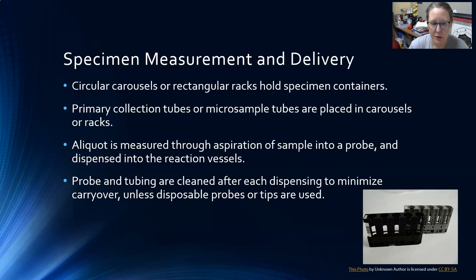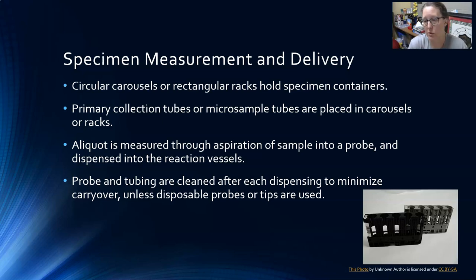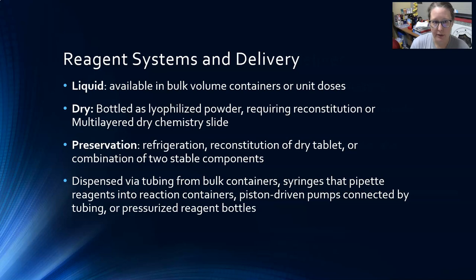The probe and tubing should be cleaned after each dispensing to minimize carryover, unless the system uses disposable probe tips — where you use one tip per sample and then dispose of it and pick up a different tip. In that case, you just have to deal with tip waste and make sure there are enough tips to feed the analyzer.